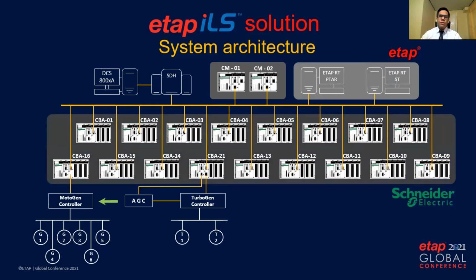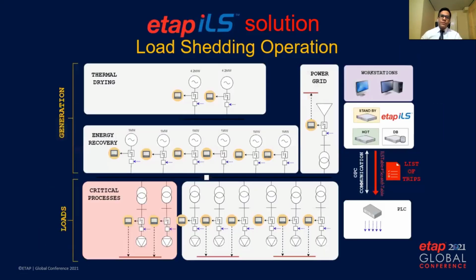Let's take a look at this example of how ILS works. First, the output of one of the energy sources of the system occurs. ETAP ILS, prior to the event, has already loaded the trip list on the master PLC. So this device, upon receiving the trip signal from the power source, sends the shedding command to the corresponding loads to restore the stability of the system, with the balance between load and generation, while the critical load is kept online.